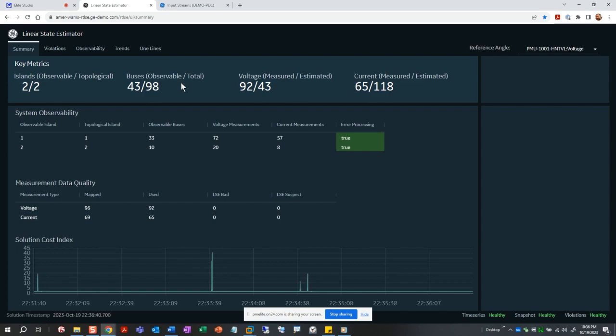So what you traditionally would use in that case is an EMS-based state estimator, which runs very routinely, runs very well, except for when you have data quality issues. So if you have PMUs in the field, or if you have a front-end processor fail, then you lose a large percentage of your PMUs on the system or the visibility into your substations, your state estimator will fail. So the linear state estimator acts as a backup to your traditional state estimator. It's using a different data source.